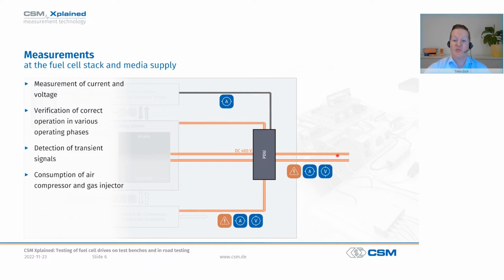Here the developers want to measure currents and voltages to find out how they behave in the various operating phases, what energy consumption, for example, air compressors, circulation fans, and the heating of the cooling systems have. And above all, what happens when these components are switched on or off, because it is precisely here that transients and harmonics can occur in the electrical system, which must be determined and investigated. For functional tests, we then also want to measure, for example, voltage and current at the output of the fuel cell drive to determine its power output.